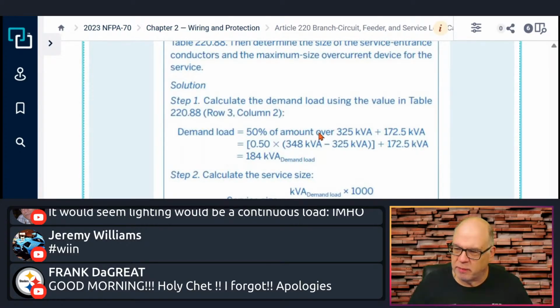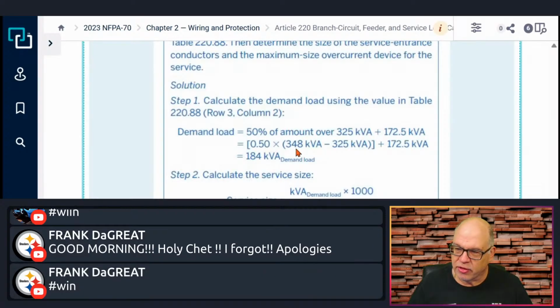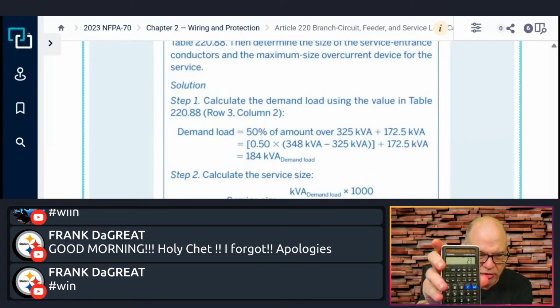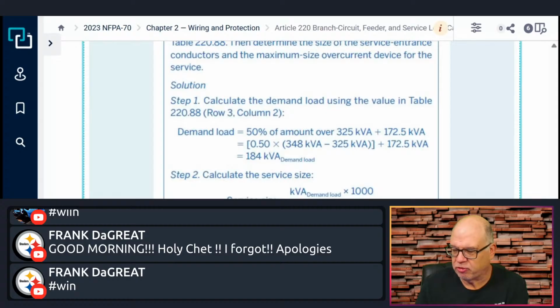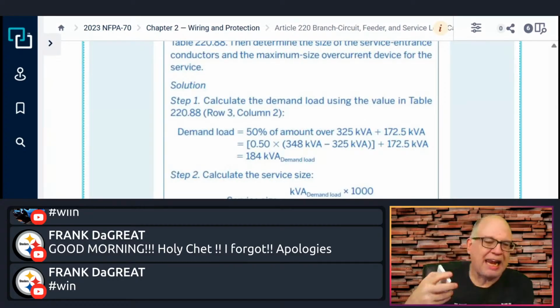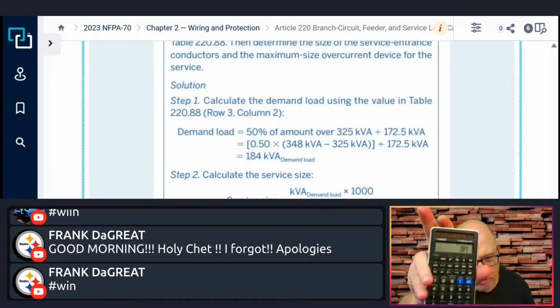All right, so 50% of the amount over, plus. So in this case, 348 minus the 325 in this example, plus 172.5 equals 184 kVA. Now, I hate when they do it like this because I like to see this. You with me? For example, I would do 348 minus 325, and that is 23. So 23 divided by 2 is 11.5, plus 172.5 equals 184. So I like to see it. That's what they mean, but you know me, we like to see it.